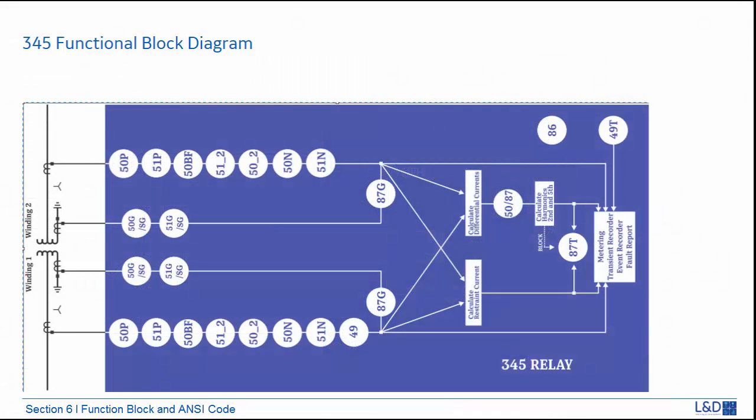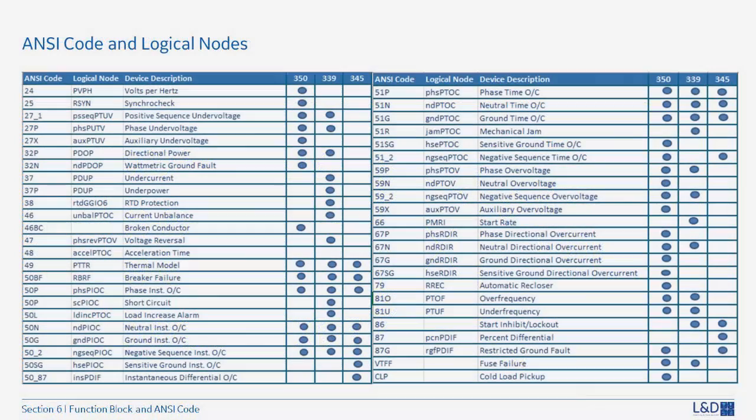In the 345 functional block diagram, there is no VT input so there are only current elements. The main protection is 87T — the percent differential — and there is also 87G for restricted ground faults. Most other elements are regular current elements like 50 and 51 — instantaneous and time overcurrent — on both winding 1 and winding 2. The ANSI code for each type of the 3 Series relay is summarized in a comparison table, showing which functions are available for each relay type and the corresponding IEC 61850 logical nodes.